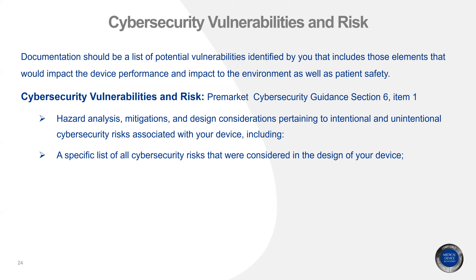When medical device vulnerabilities are not addressed or remediated, they can serve as access points for entry into hospitals or healthcare facility networks. Vulnerabilities may lead to compromise of data confidentiality, integrity, and availability — a safety issue. NIST and TIR 57 standards are good resources to help identify vulnerabilities applicable to your device. This part of documentation must cover the cybersecurity risks considered in the design of your device — risk or potential hazards, severity of harm, device design consideration, risk mitigation methods, and risk acceptance criteria.